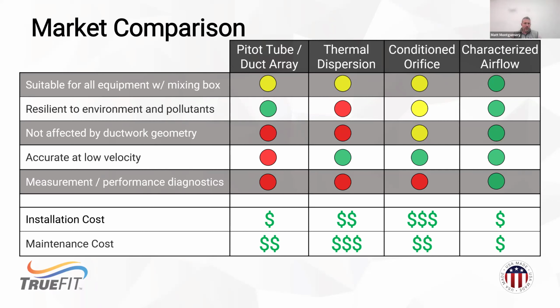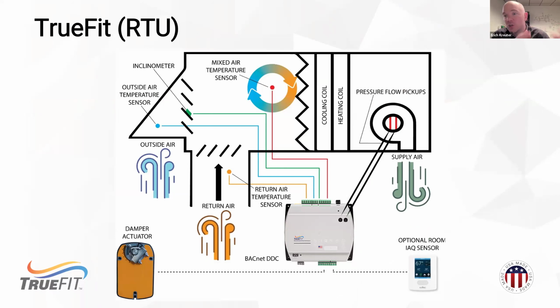Awesome, Eric. Looks like we have one question, and you might have hit this while we were going: if we're accurately measuring the total supply airflow and the inlet mixed air temperature, why do we need the inclinometer? For sure. So we could run those temperature equations in real time. That's exactly what we do for our diagnostics. However, there are many times where we don't have delta T. And if we don't have delta T, we can't run those numbers, which is why we need the performance curve and we need to know where we're at in the curve, which is what the inclinometer tells us. So those two things are key to producing measurements at any time, regardless of the delta T that you actually have in your system.